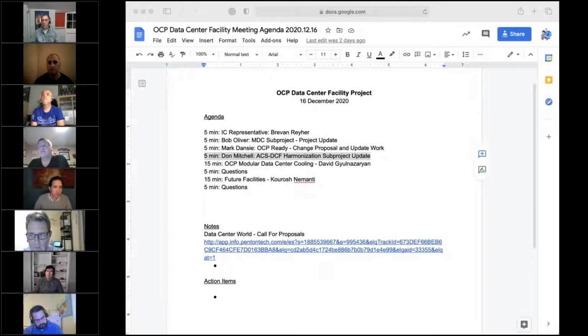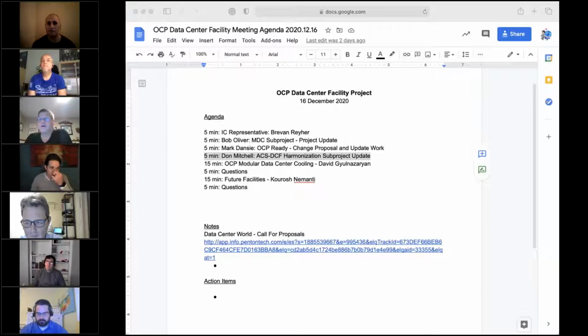The reason this ends up being a DCF discussion is that your design considerations for condensation are dramatically different if you know the liquids going through your data center will be above dew point at all times. ASHRAE does not mandate that the liquids running through the data center are above dew point. They mandate that the temperature is maintained at a non-condensing environment for the equipment, but the historic method has been taking cool liquids, running them through, and insulating them. The negative is you can have cool liquids operating below dew point.